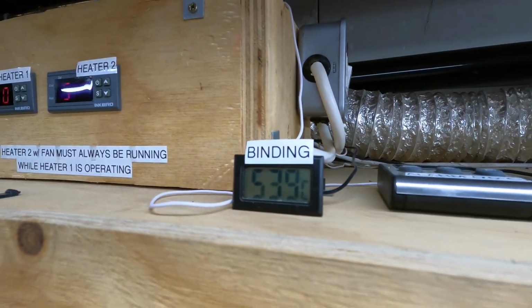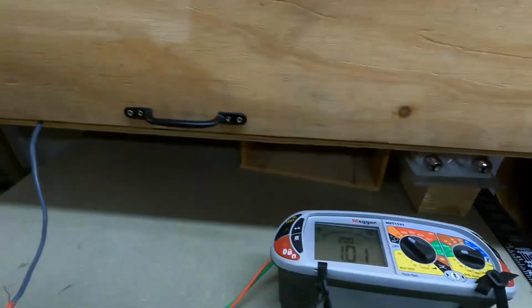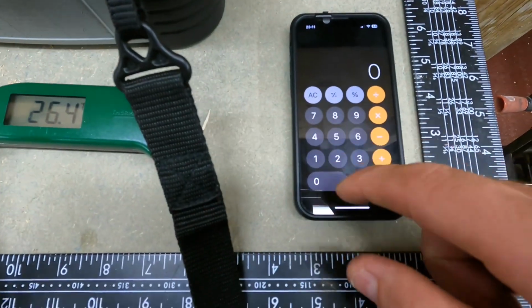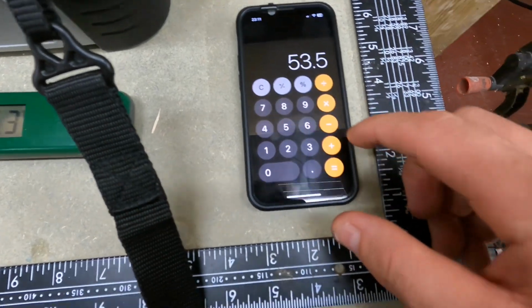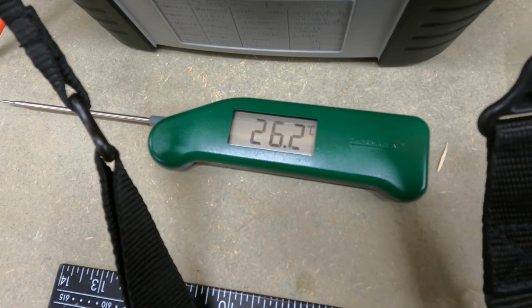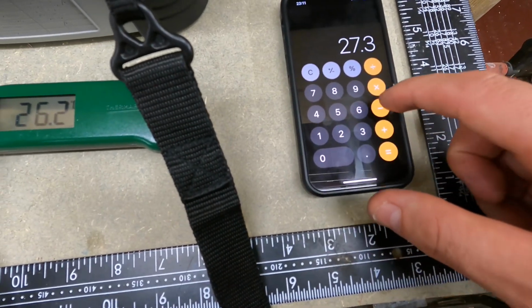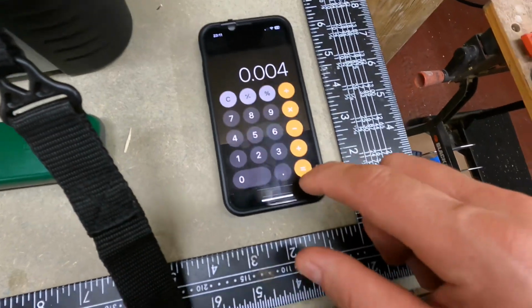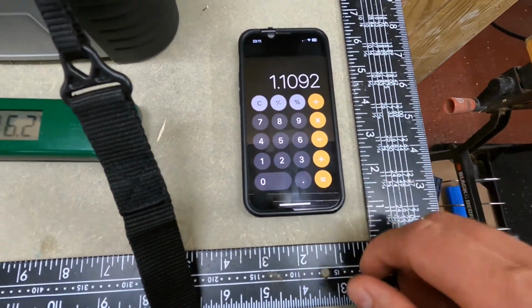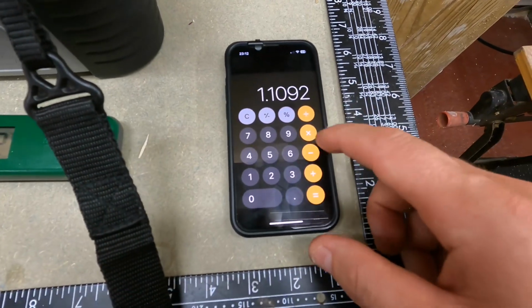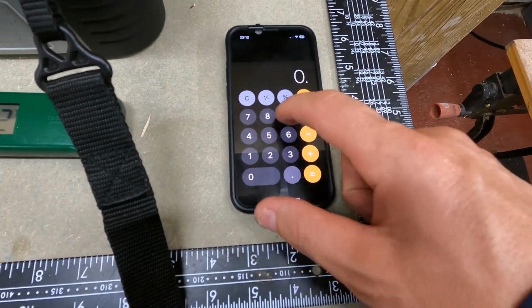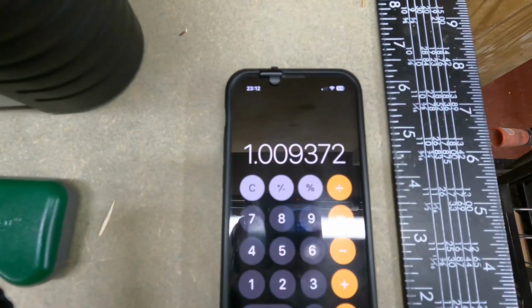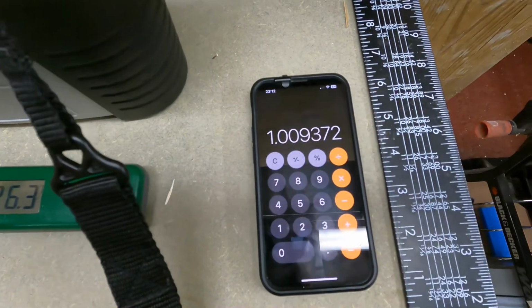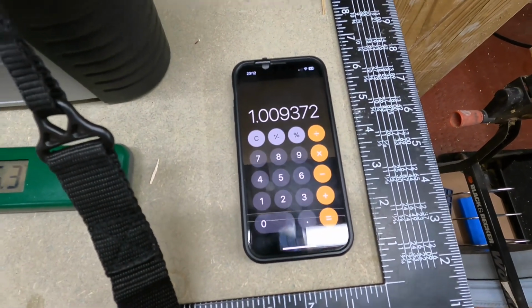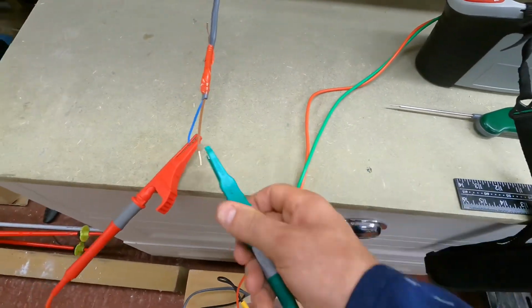Interesting thing—if we take the cable temperature as 53.6, 53.5, and do 53.5 minus room temperature, say 26.2, times 0.004—that's the formula for cable resistance—then if we multiply that factor by 0.91, our room temperature reading, we get basically equivalent readings. So the math works, and the science works.